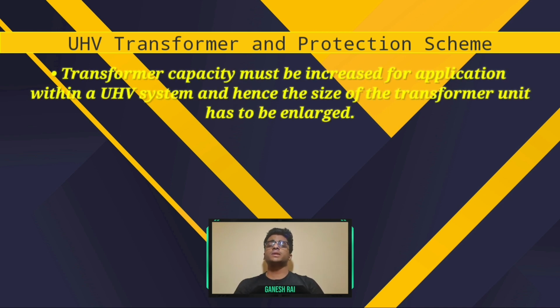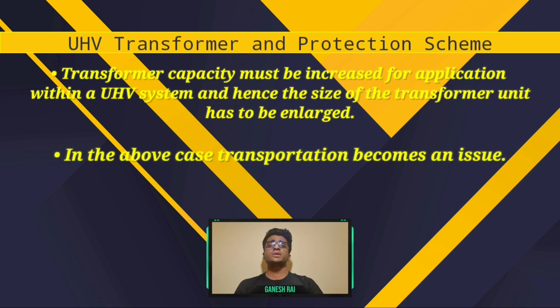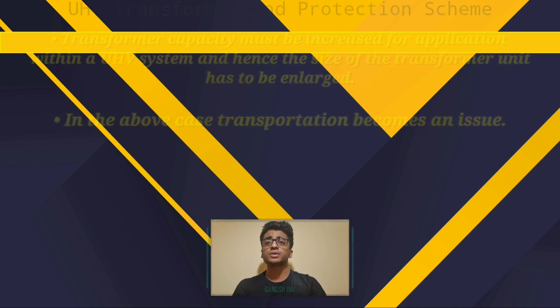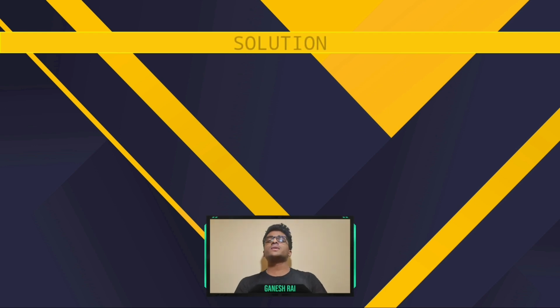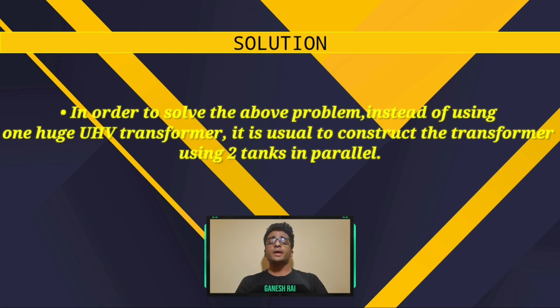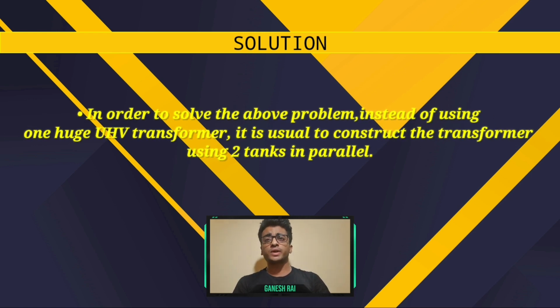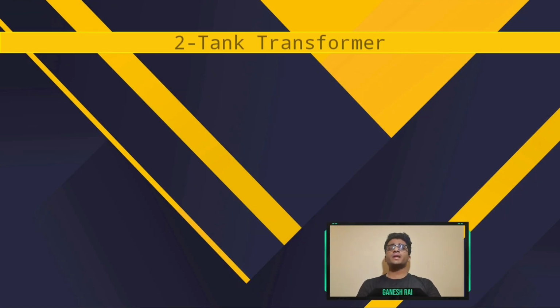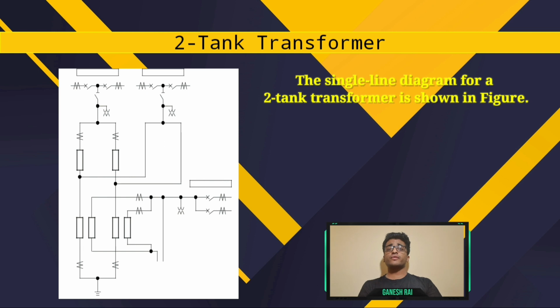Transformer capacity must be increased for application within a UHV system, and hence the size of the transformer has to be significantly increased. But when we enlarge the size of the transformer, one huge issue comes into picture, that is transportation. So when there is a problem, there's always a solution. In order to solve this problem of transportation, instead of using one huge UHV transformer, it is usually considered to construct the transformer using two tanks in parallel. The single line schematic diagram for a two tank transformer is shown in the figure.